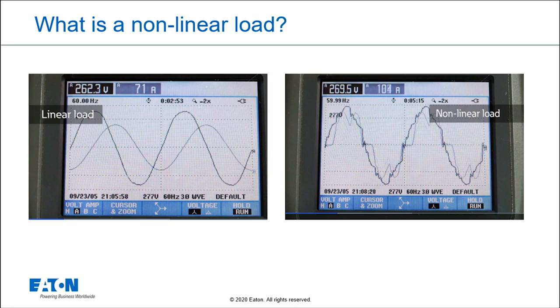On the other hand, a non-linear load, the current does not look like the voltage. And in this case, we have current that's really screwing up the voltage because harmonics come from the loads. And as we pull that current through the system, we create voltage distortion. So non-linear loads create current distortion and then cause voltage distortion.